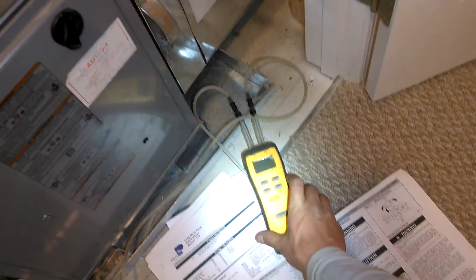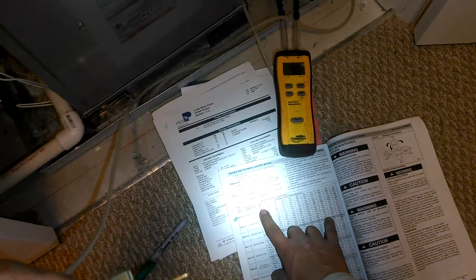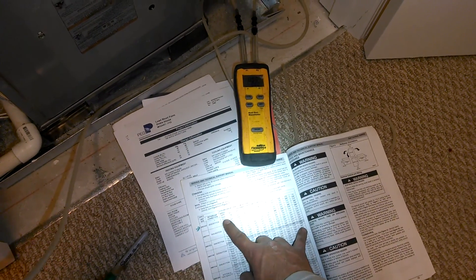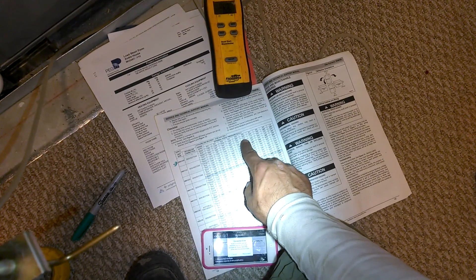So what I have here — I'm going to pull this out. I checked it two different ways. I checked it on the black terminal and I'm right here. Checked it on the blue. I don't know if y'all can see that, but I checked it on the black and I'm like 835 CFMs. I checked it on the blue and I'm right at like 770, 715. I'll show you.